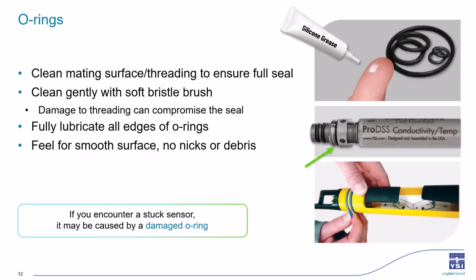Here's another thing to keep in mind. If you have a sensor that's stuck in your bulkhead, it's probably because the O-ring on the retaining nut has become snagged in the threading. That green arrow there is where you can see that little O-ring on the retaining nuts. So that little O-ring here is probably causing that issue. And you might just have to brute strength the sensor out of your instrument, as carefully as you can, and then clean it, and then remove that sensor and replace it with a new one.